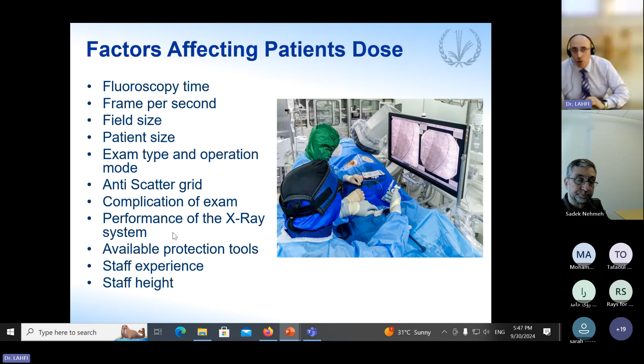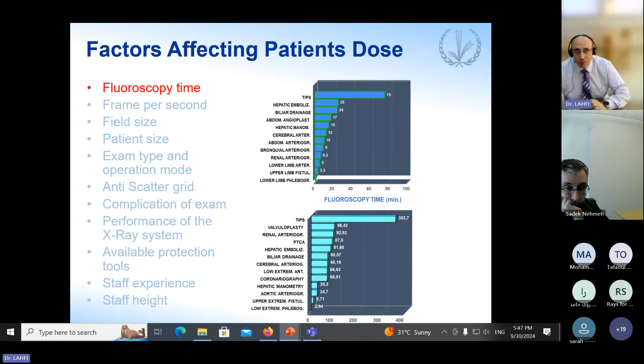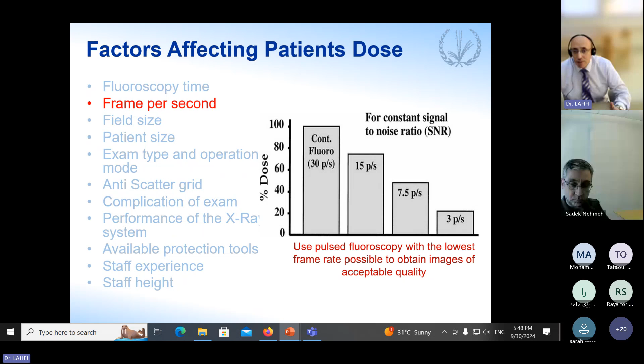First of all, fluoroscopy time. Fluoroscopy time is very important. The radiologist may keep in mind to reduce the time of fluoroscopy. So less time is better for the patient dose. This can also be done through the frames per second, reducing the fluoro frame rate from 30 frames per second down to 15, or down to 3 frames per second, which can contribute to lower doses and may also obtain acceptable image quality. So the high frame rate is not always necessary for all interventional procedures. The field of view also: decreasing the field of view by a factor of 2 may increase the dose rate by a factor of 4. So we have to take it into account.